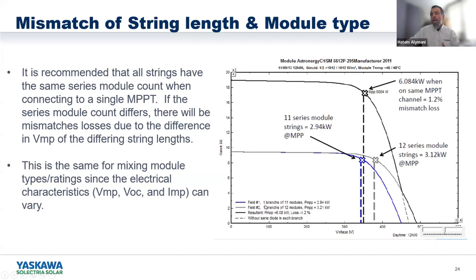So let's assume that we have one branch of 11 modules, and the maximum power for this string is supposed to be 2.9. And then we have another branch, which is 12 modules, and the maximum power point is supposed to be 3.2. Now, if we put the first string in MPPT1 and the second string in MPPT2, we're perfect. We're going to get the maximum power out of the two strings.